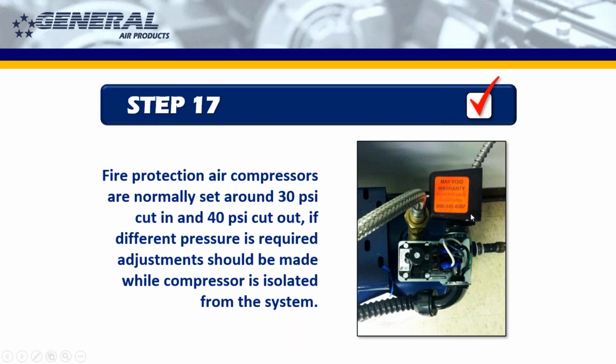Now notice the scary sticker on here that says may void warranty. That is there to scare you into calling us about your pressure switch adjustment. So call the 800 number. I have this model number. I have this pressure switch on here, whatever it is. What do I do? Which screw do I turn to adjust this? This is a common phone call we get. And what scares me is it should be more common.